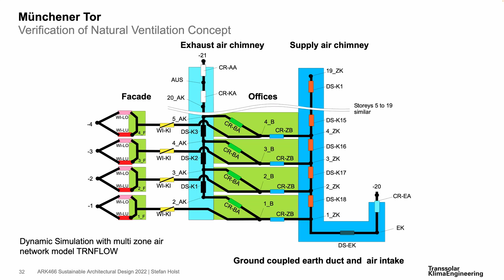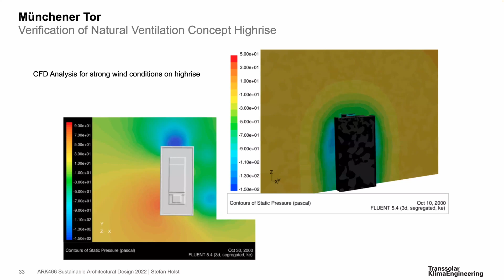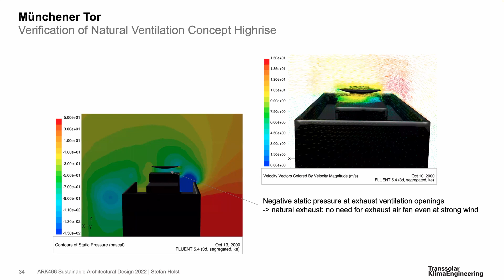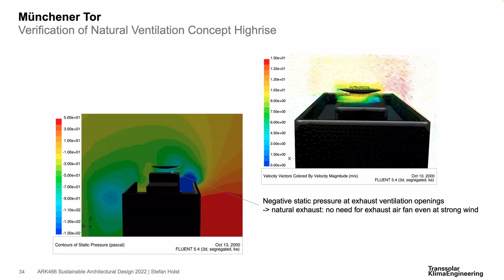And we said, no, we don't think we need that. And then we had to prove that we never get wind in that exhaust shaft that would stop the system from working. So we did a couple of airflow analyses with computational fluid dynamics programs, and showed that we always have negative pressure on top of that chimney, and actually convinced the client to leave out that system. And the mechanical engineer complained, but in the end, they agreed. So we don't have a fan there. We have a little fan in the basement to pump the air through in summer, but that's about it.